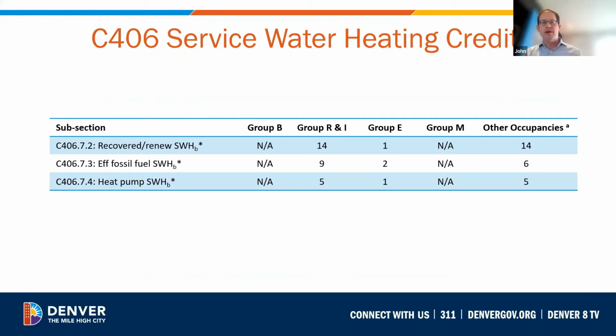Service water heating. High efficiency service water heating equipment can qualify for a large number of credits, especially for Group R and I projects. Energy credits are available for service water heating systems that derive at least 70% of heating energy from a renewable source. That renewable source could either be a solar hot water system or recovered heat from a heat recovery chiller, such as condenser heat recovery, or even heat recovery from a process load or waste heat stream.